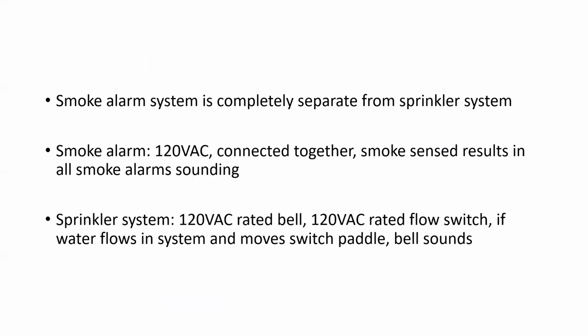So the smoke alarm is completely separate from the sprinkler system. The smoke alarm is 120 volt AC connected together in parallel. Smoke sensed results in all smoke alarms sounding. The sprinkler system is a 120 volt AC rated bell, 120 volt AC rated flow switch. If water flows in the system, which would be caused by one of the glass bulbs bursting due to heat, and moves the switch paddle, the bell will sound.